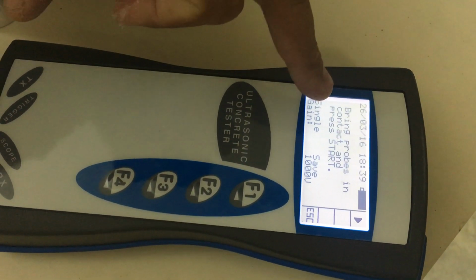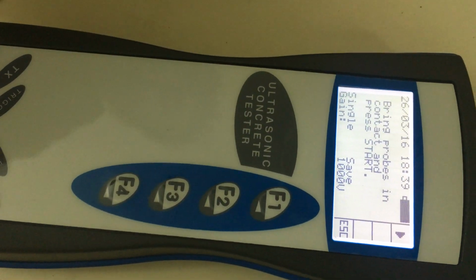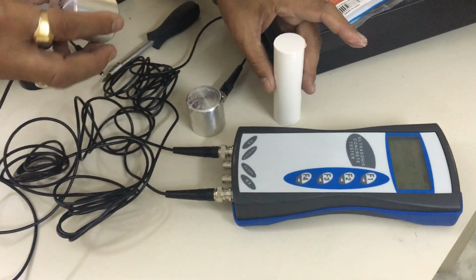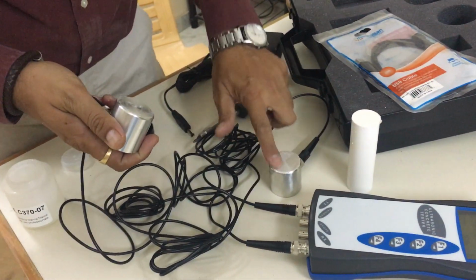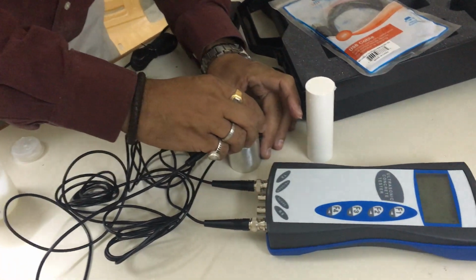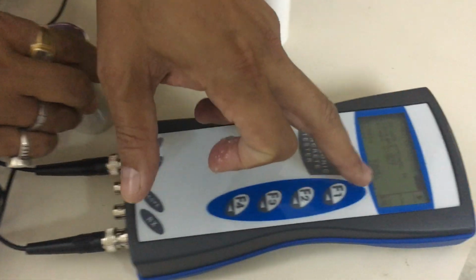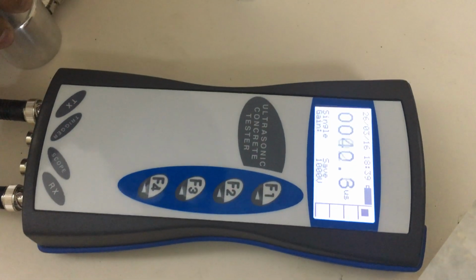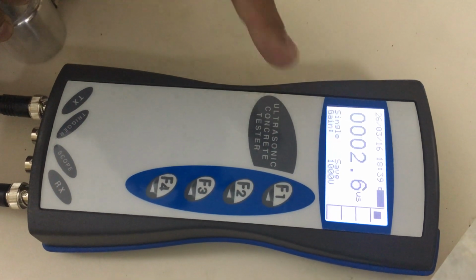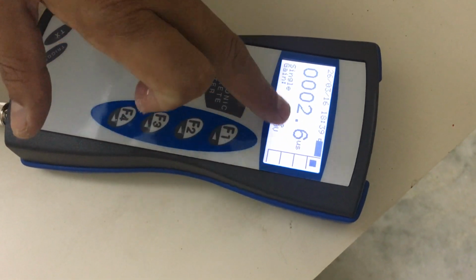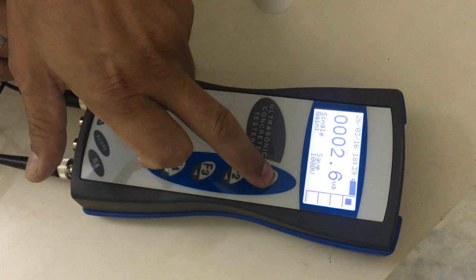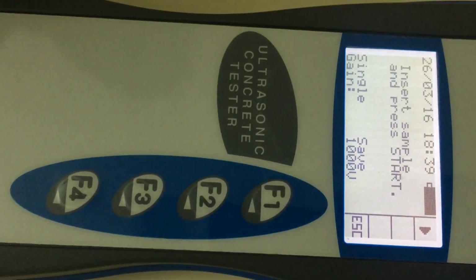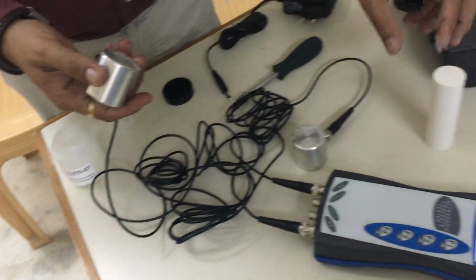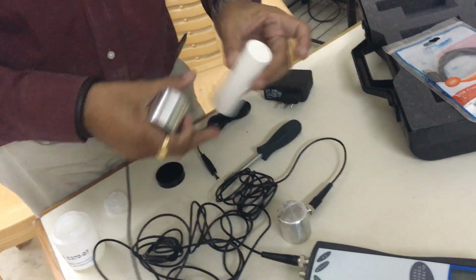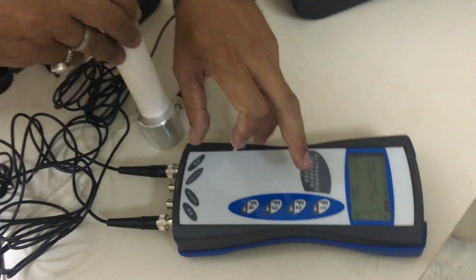Now you can see that it is mentioning: bring the probes in contact and press start key. So without the sample, it's asking me to bring the probes in contact. So I am bringing the probes in contact. Okay, now press start key. F1 is the start key. Still the process is going on. Just press the stop key after this. F1 acts as the stop key. Whatever the value, just note it down, but make sure that there is good contact. Now another message comes: insert a sample and press start key. For our calibration, our sample is a 42.5 microsecond standard rod. So I put the standard rod in between and press start key once again.